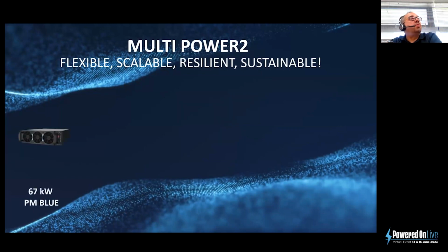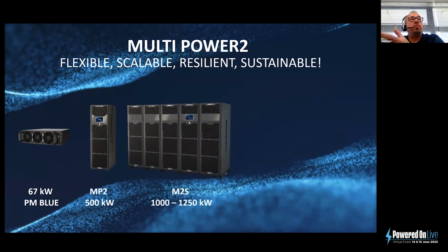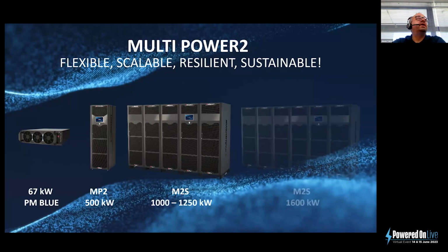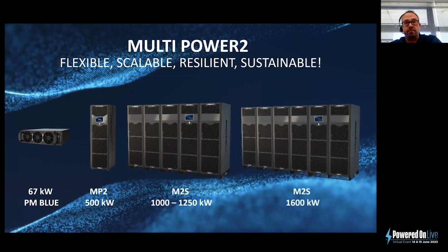Basically, the main building block of this UPS system is formed around a 67 kilowatt power module. That power module is then matched to 3 specific power cabinets. You have a 500 kilowatt power cabinet for small applications. You've got a 1 and 1.25 megawatt power cabinet for larger installations. And again, you then have a 1.6 megawatt frame for, again, larger installations, and all of these cabinets can be put in parallel in order to provide additional resilience at a cabinet level.